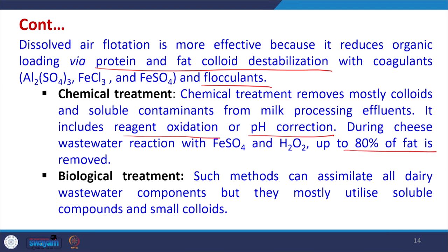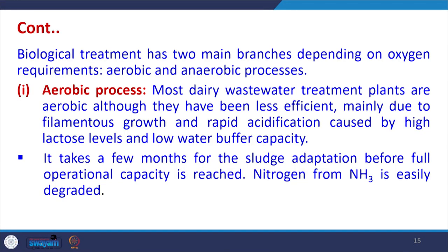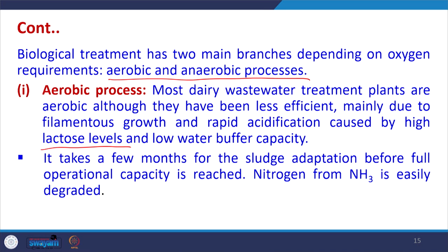Biological treatment can assimilate all dairy wastewater components but mostly utilizes soluble compounds and small colloids. This includes two approaches based on oxygen requirements: aerobic and anaerobic processes. Most dairy wastewater treatment plants are aerobic, although they have been less efficient mainly due to filamentous growth and rapid acidification caused by high lactose levels and low water buffer capacity. Aerobic treatment takes a few months for sludge adaptation before full operational capacity is reached.